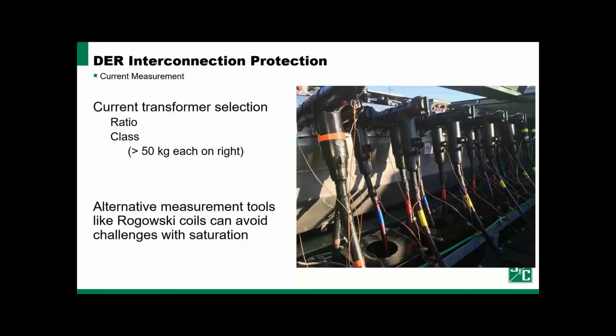Another challenge that we face in microgrid protection is simply measuring current. As we highlighted earlier, in microgrids and in DER penetrated systems, fault current levels can vary significantly. Faults contributed to by local generation, especially inverter based generation, can have much lower magnitudes than our normal grid-tied fault current magnitudes. And to detect these, we need to select our current measuring tools consciously and effectively.